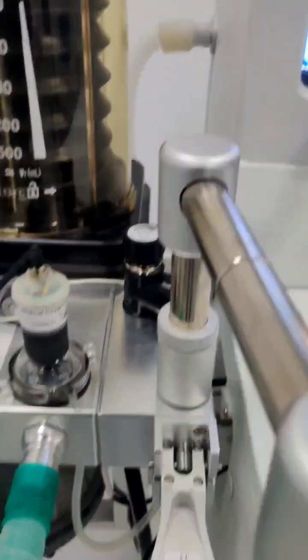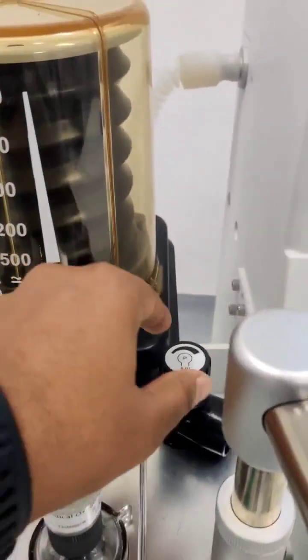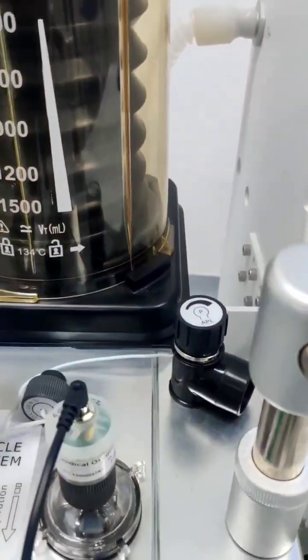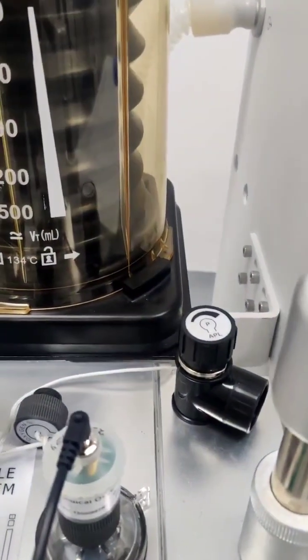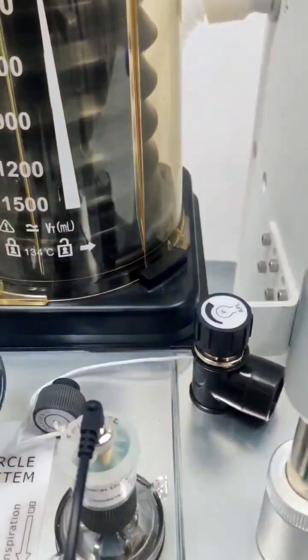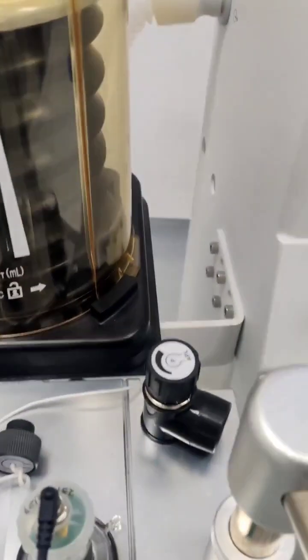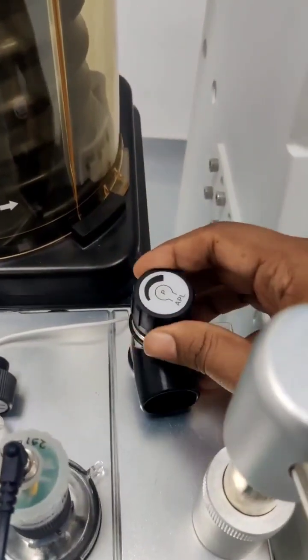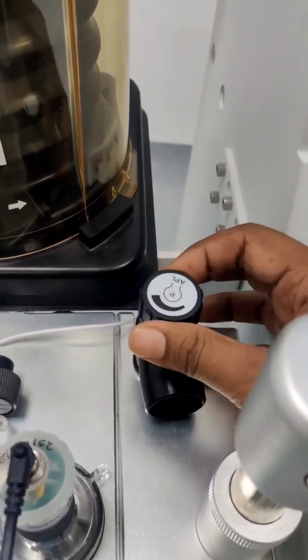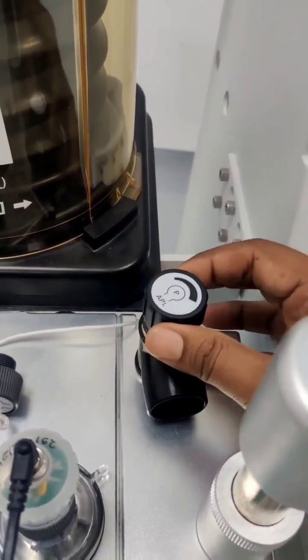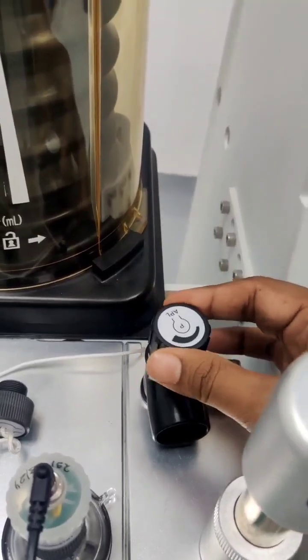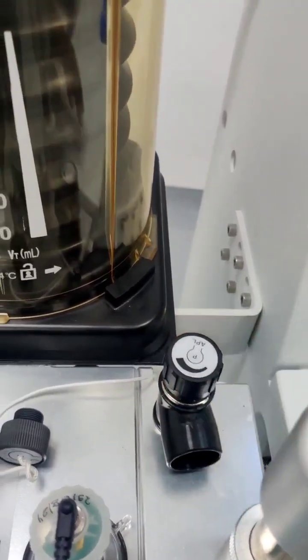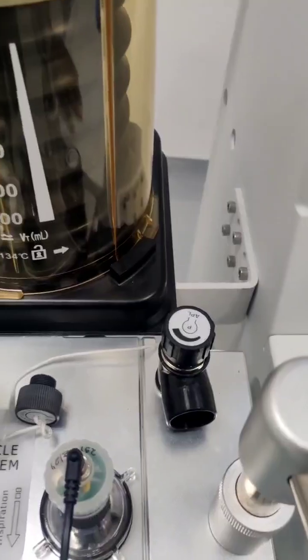And when the machine is on the manual ventilation mode, this is the APL valve which will get activated. So you can set the pressure of the patient with the help of this APL valve over here, that is the airway pressure limiting valve. Whatever pressure is generated in the patient's lungs, or the airway pressure generated, that can be limited with the help of this APL valve by rotating it clockwise and anti-clockwise.